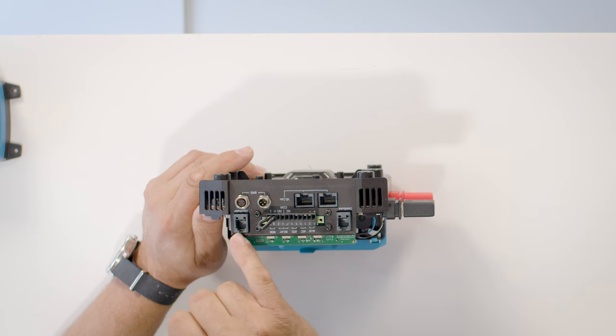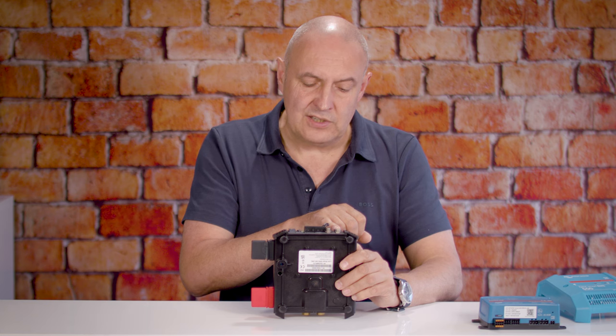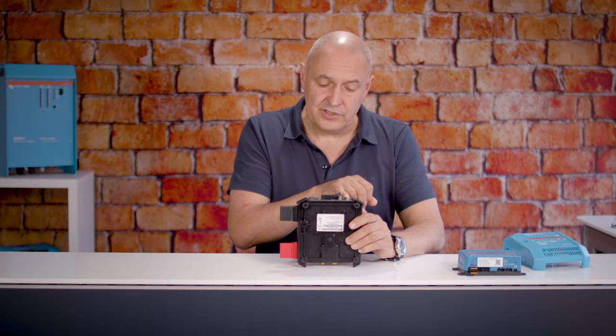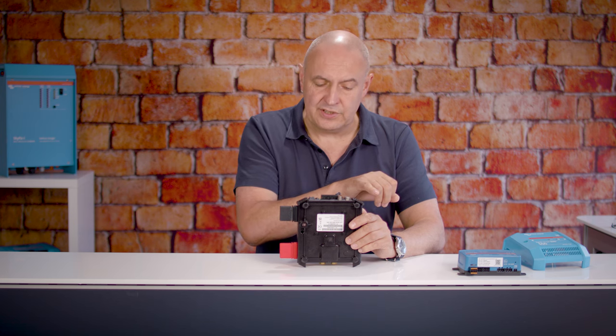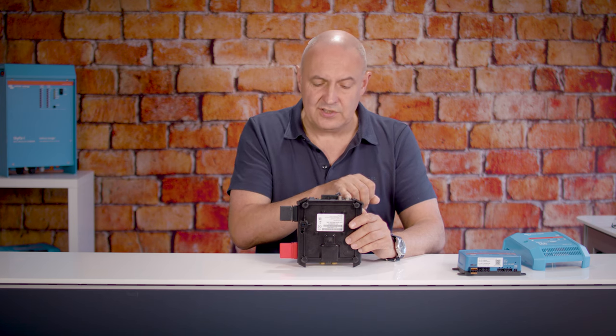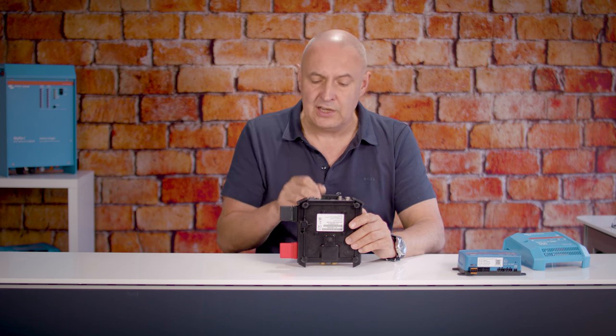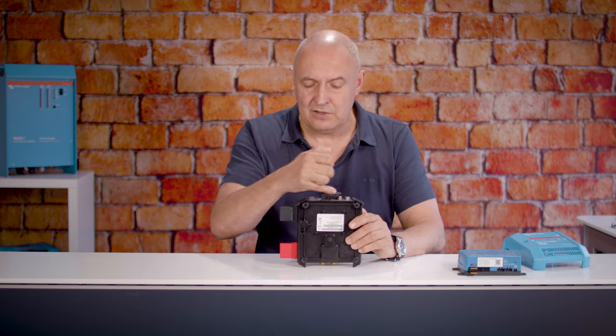We've got these two little RJ10 ports at either end, and this is how the fuse status of the Lynx distributors is communicated back to the BMS. So there's just a little link cable that links across to the distributor, and this carries the data on fuse status back, and this is then communicated back to the system over VE.Can.